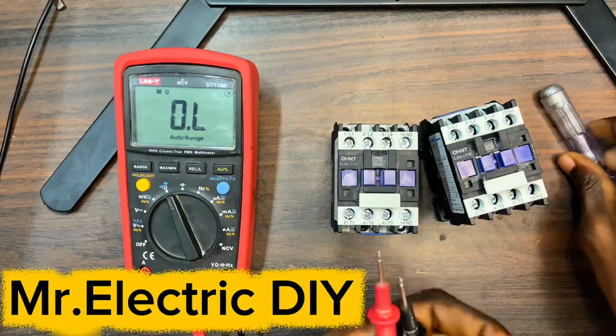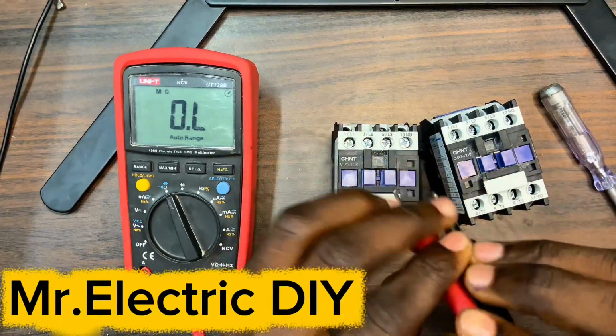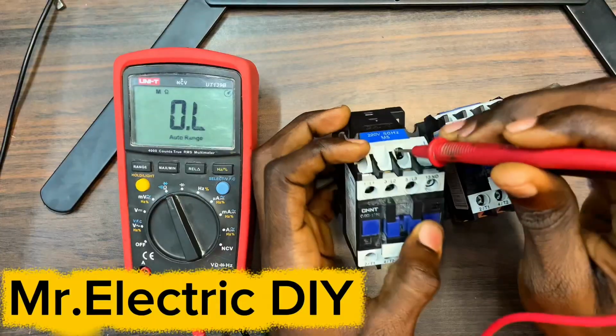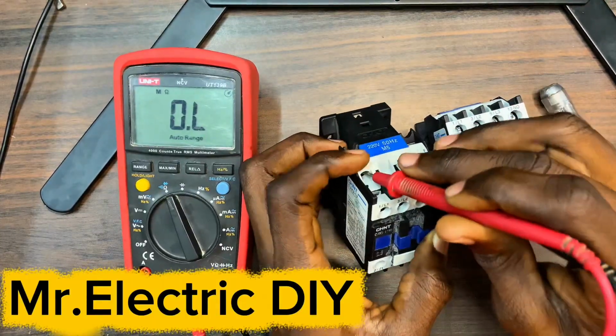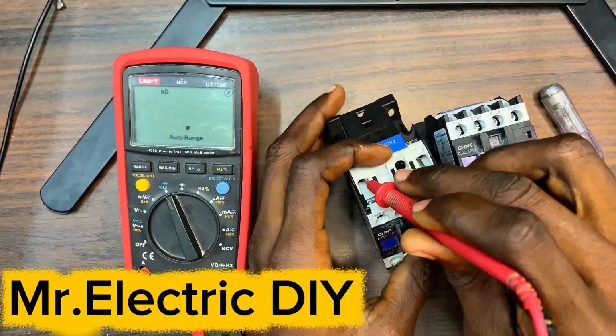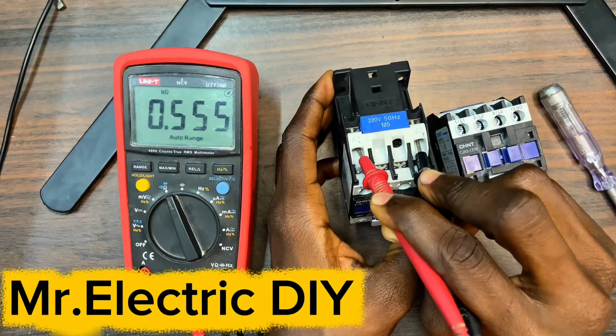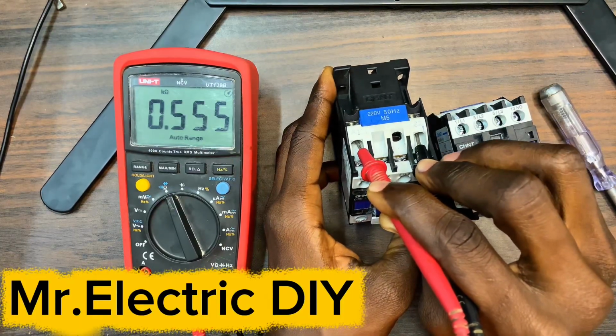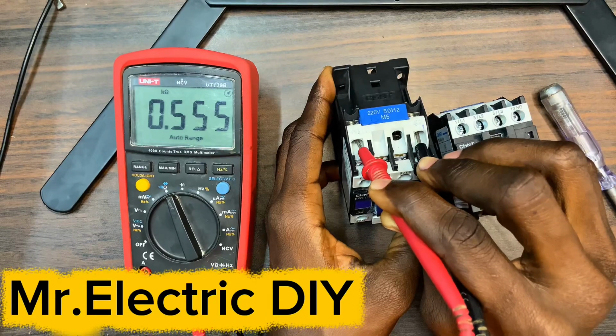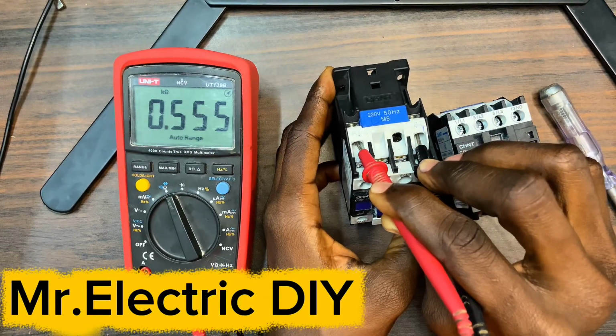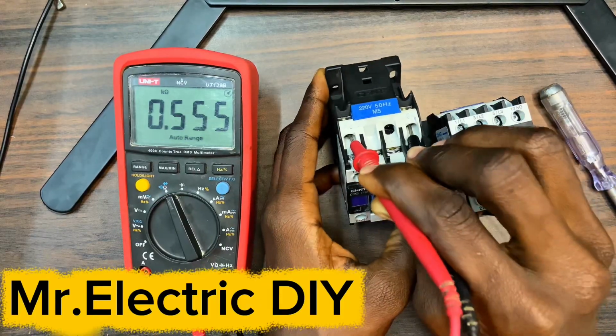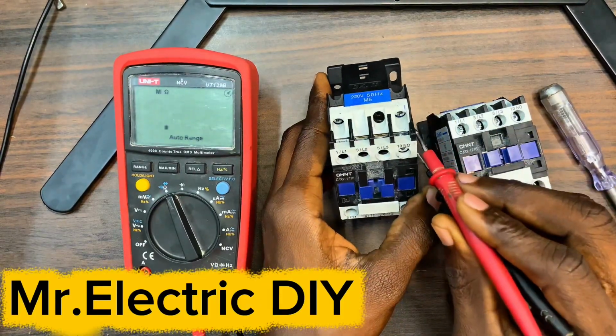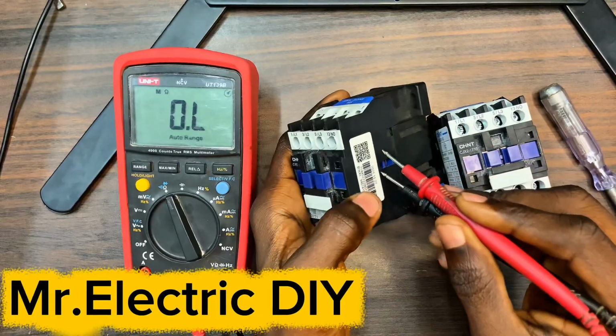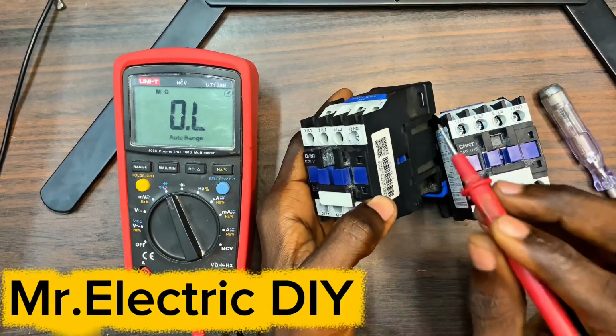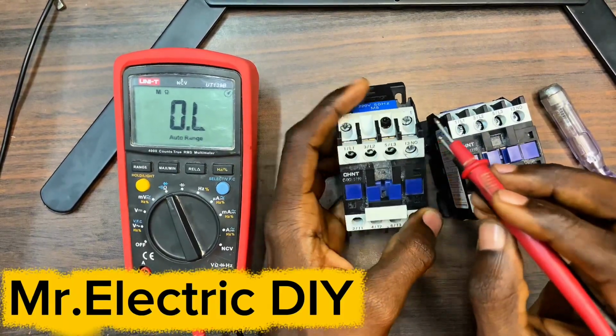So what we will do is to insert the leads to the terminals, that is the coil terminals. Now we have 0.555 kilo ohm, 0.555 meaning 555 ohms. That is the ohmic value of the magnetic contactor coil we have in here. That is the ohmic value of the contactor coil.